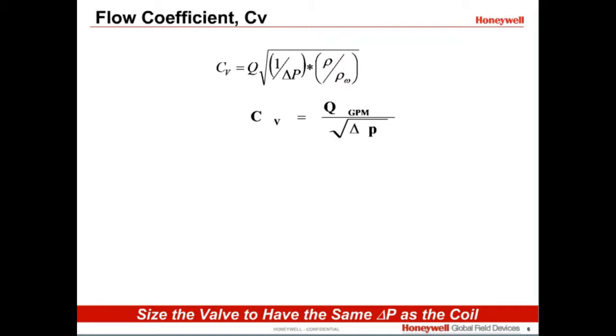This leaves the CV equation to be the flow rate in GPM divided by the square root of the pressure drop. If the pressure drop is not known, you can use some rules of thumb. 3 to 5 psi is often assumed for small to medium-sized coils. To make the math easy, you may use 4 psi as the pressure drop and estimate the CV by taking the flow rate in GPM and dividing it by 2.